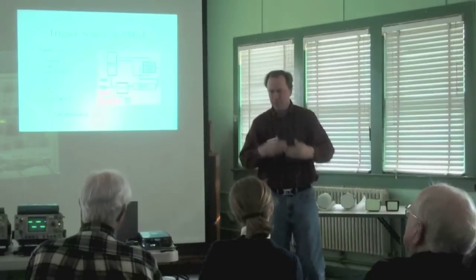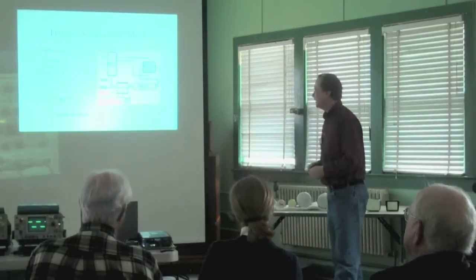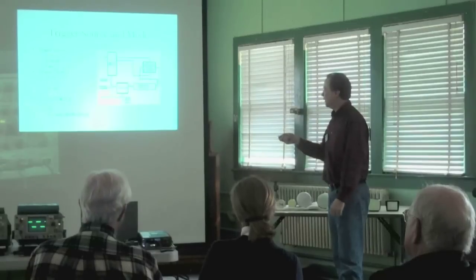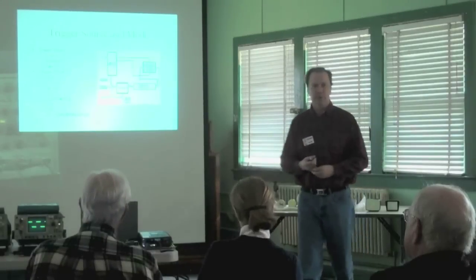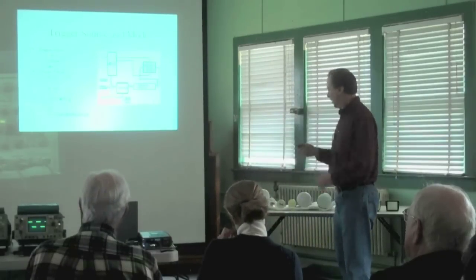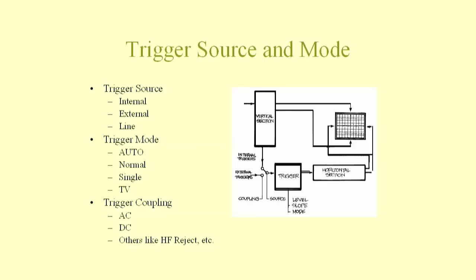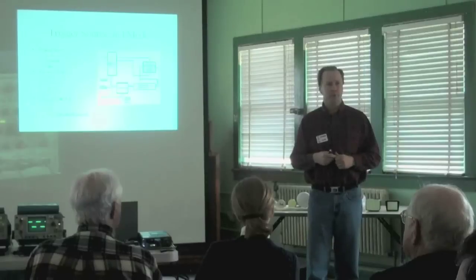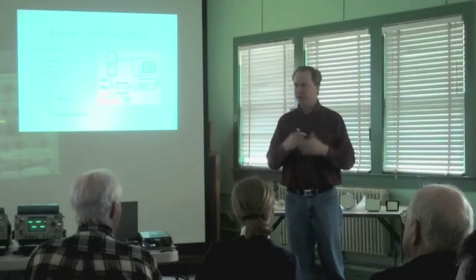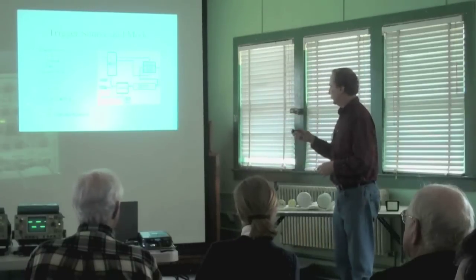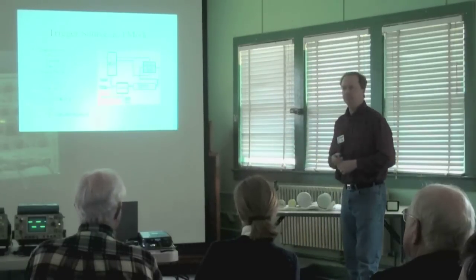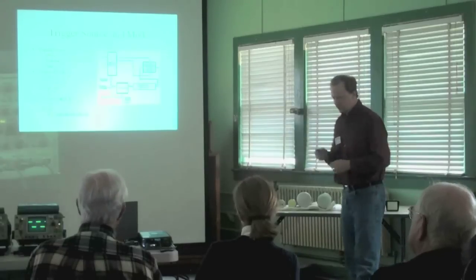A little 10-pack of film you stick behind them, but that's where you typically use things like single channel, single sweep, I should say. Now some of the scopes you'll see have a special TV triggering mode, which allows you to trigger on the horizontal or vertical sync pulses of an NTSC video signal. We've got an NTSC signal generator back there, so you can play with some of that. But that's the TV trigger. Not all the scopes have that. It was an option on some scopes.